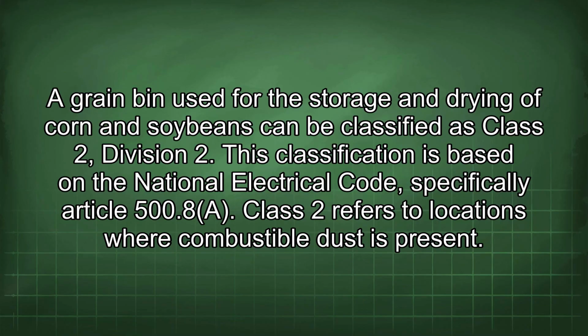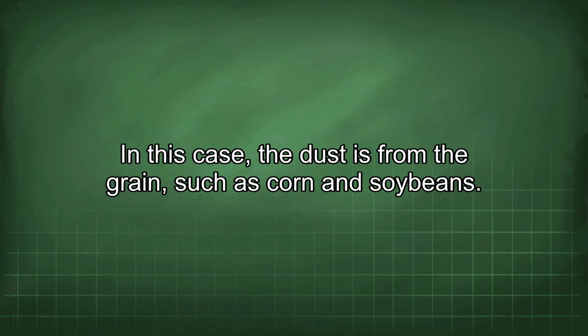A grain bin used for the storage and drying of corn and soybeans can be classified as Class 2, Division 2. This classification is based on the National Electrical Code, specifically Article 500.8(A). Class 2 refers to locations where combustible dust is present. In this case, the dust is from the grain, such as corn and soybeans.